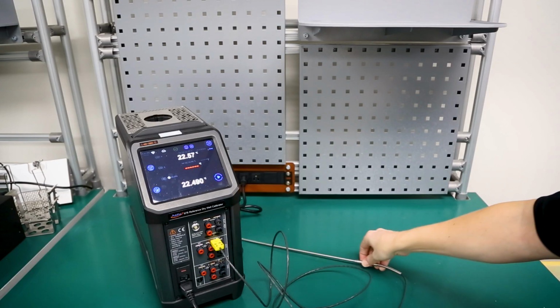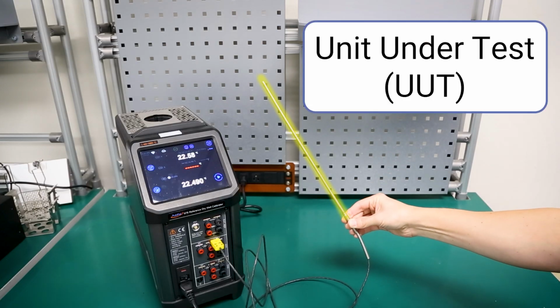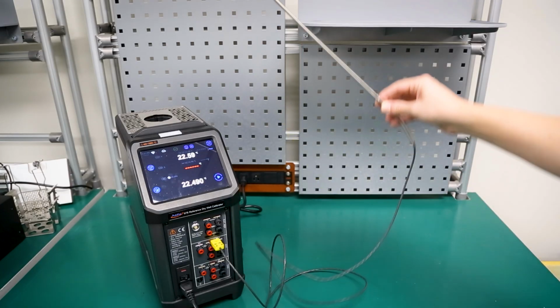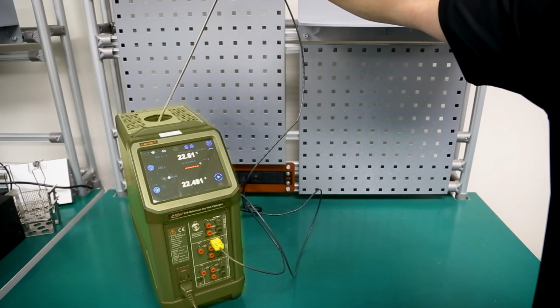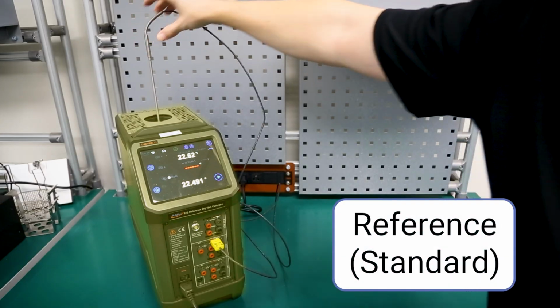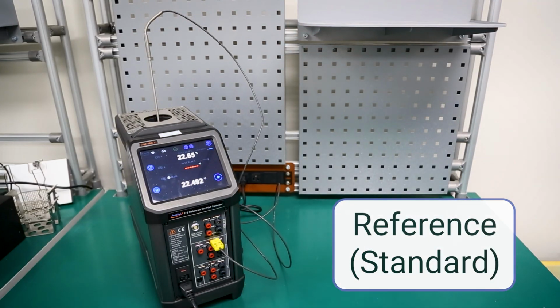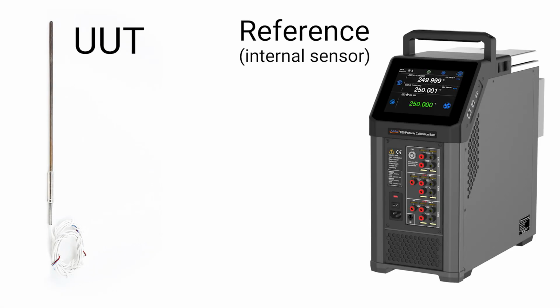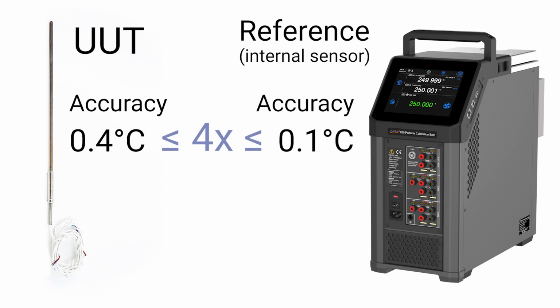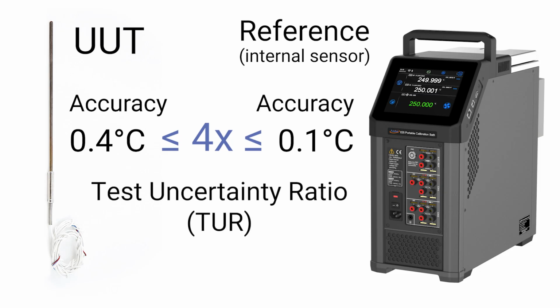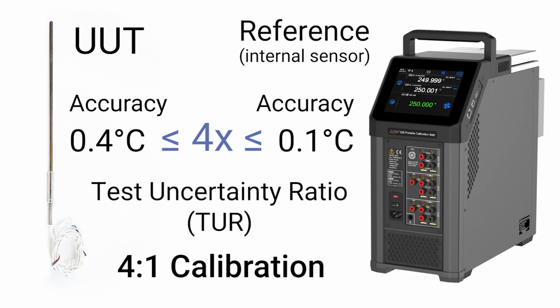To do this, a technician will compare the reading of the unit under test, or UUT, to the reading of a more accurate and calibrated sensor, often called a reference or standard, across a number of different temperature points. Calibration procedures will vary by industry, but a general rule of thumb is to use a reference that is at least 4 times as accurate as the UUT. This specific test uncertainty ratio is often referred to as a 4-to-1 calibration.